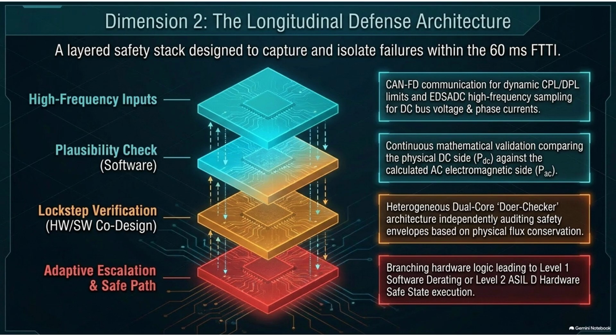No, it's highly specific. It is the calculated threshold before massive overcurrent causes the internal temperature of the lithium-ion cells to reach a point of no return. So any longer and you risk thermal runaway. Yep. Exactly. Thermal runaway or severe irreversible degradation of the battery contactors. The system must recognize the fault, process it, and physically halt the overcurrent all within that 60-millisecond window. Okay, so what is the first layer of this 60-millisecond defense?